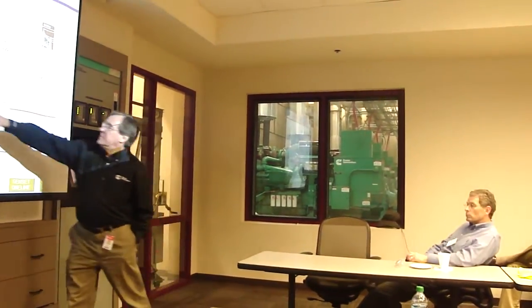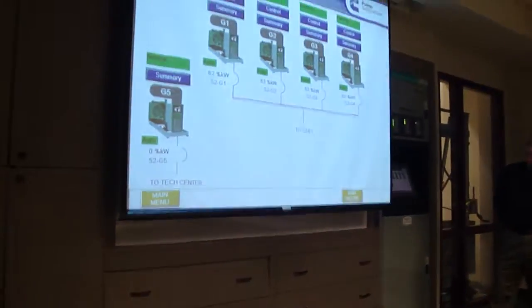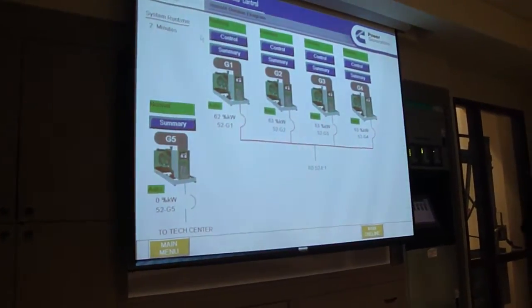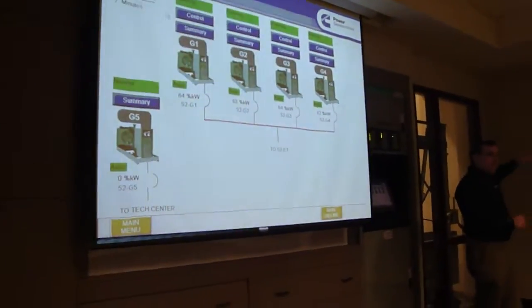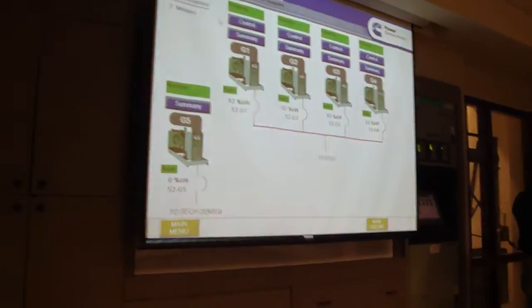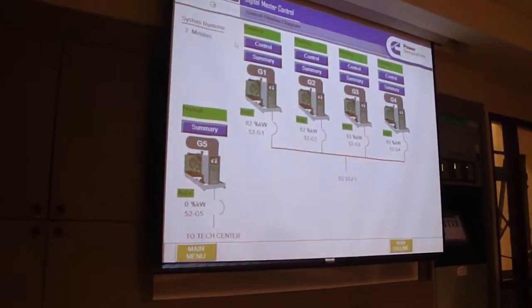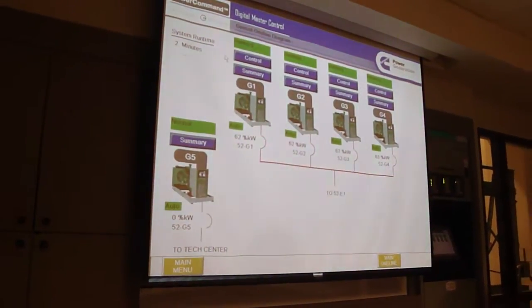Right now you can see here we're importing about 800 kilowatts from the utility. Let's go look at these generators. They're each running at about 60%, sharing load equally. And that's done with communication between each of the generators — they communicate over a twisted pair communication line and share load.